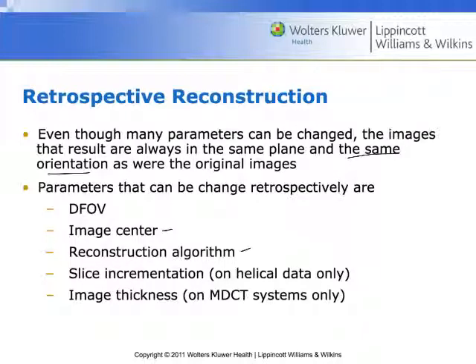We can change the slice incrementation only if we're using a helical or volumetric data set. If it was acquired axially, we will not be able to change the slice increment, or we will get a stair-step kind of artifact. We can also change the image thickness if we're using a multi-detector CT system. Very often we'll want to use a thin slice for scanning and then reconstruct thicker slices for viewing, because then in storing those images it's going to be more easy to manage those files, and we will maintain spatial resolution.